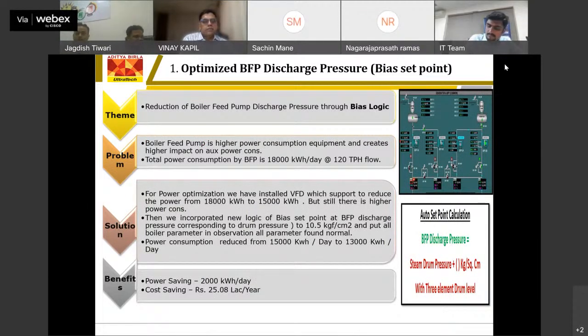Good morning, sir. This is our first best practice, which is the BFP discharge pressure optimization through our bias logic. In this logic, our BFP discharge pressure will be set to the steam drum pressure plus the set point which will be given to maintain our discharge pressure while controlling our drum level, sir. Through this process, we can optimize our energy by near about 2000 kWh per day, which gives a saving of 25 lakh per annum, sir.